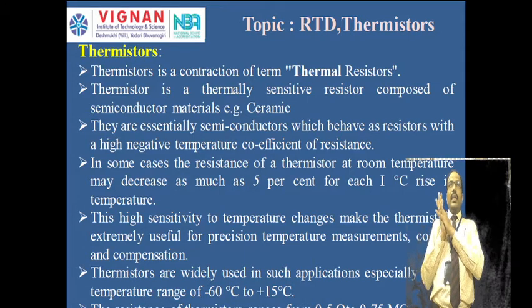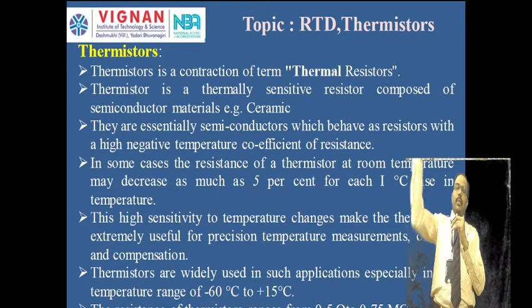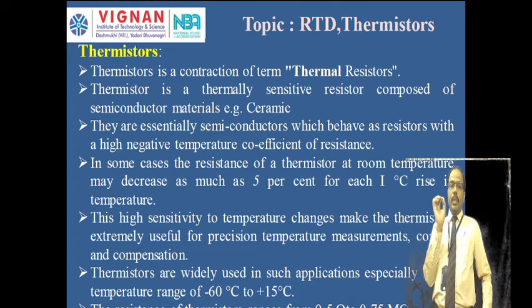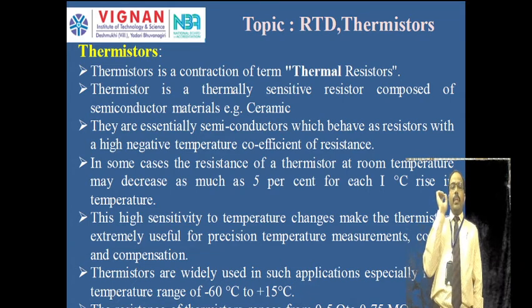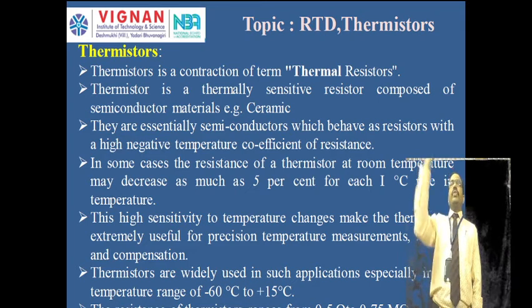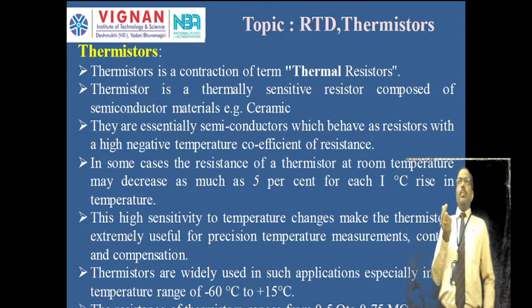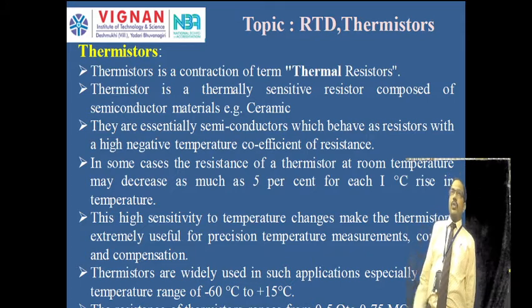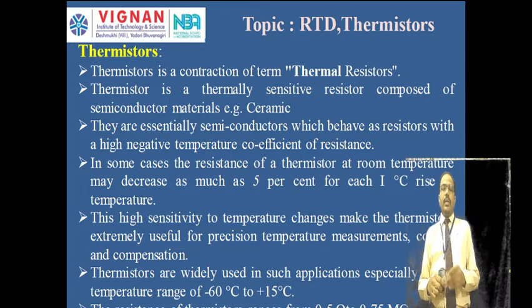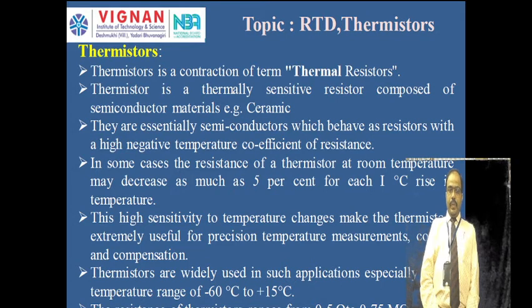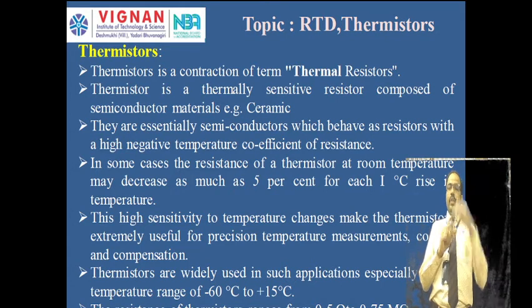Thermistors have high sensitivity compared to RTDs and thermocouples. This high sensitivity makes thermistors extremely useful for precision temperature measurement, temperature control, and compensation. Very small temperature changes of 0.1 or 0.01 degrees centigrade can be measured using thermistors. In most applications, thermistors are used in the temperature range of minus 60°C to 15°C, and their resistance ranges from 0.5 ohms to 0.75 megaohms.